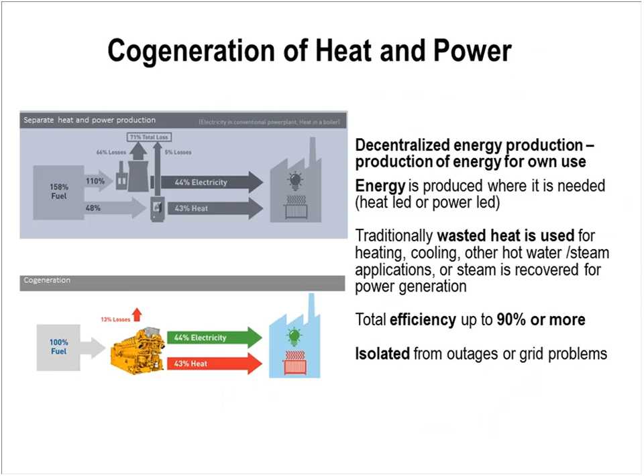If I've got my electric power, you know the jacket water coming off that engine is going to be somewhere between, typically, in that 195 to 210 range. There are some engines capable of higher systems so you can take that water off the engine, flash it to steam outside the engine, and use it there, typically at 15 psi.